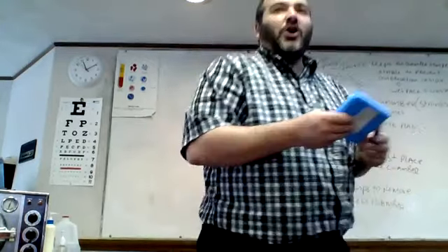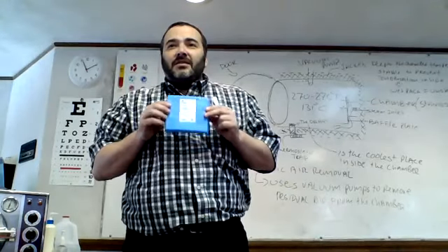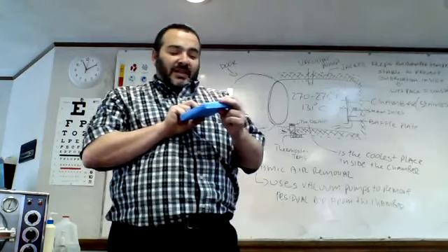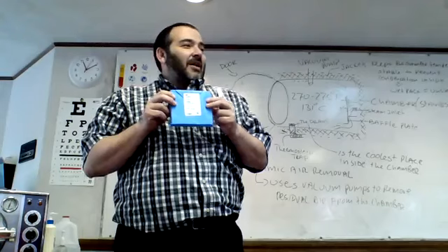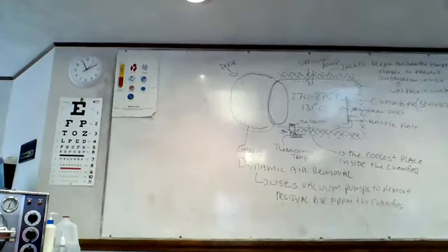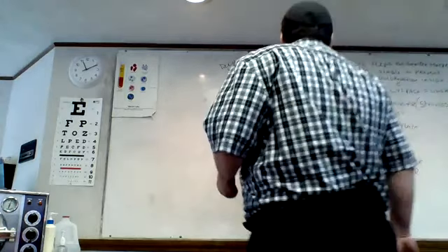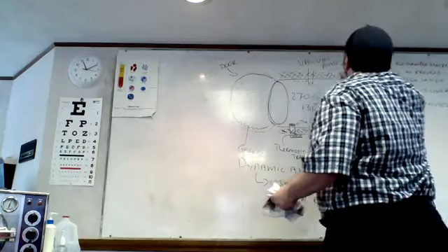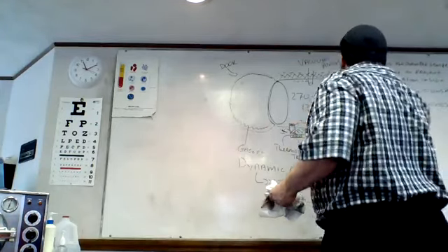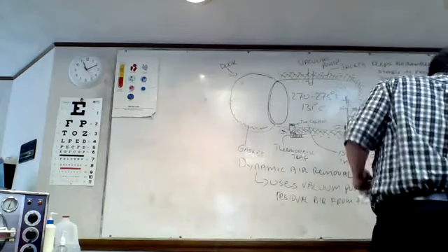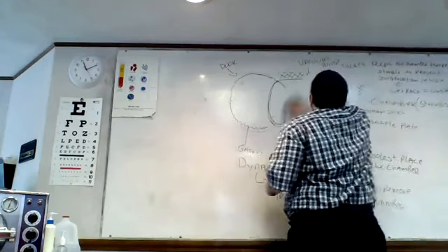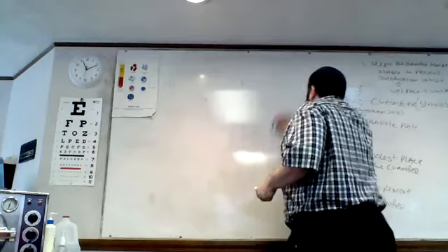In any case, what I want to show you here is one more test. Dynamic air displacement systems use another test. All right, pass it around. You can't see what's inside, but I will tell you what this is. Notice the name on the package. What does it say? What's the name of the test? Bowie Dick test. That's right. It's very important.